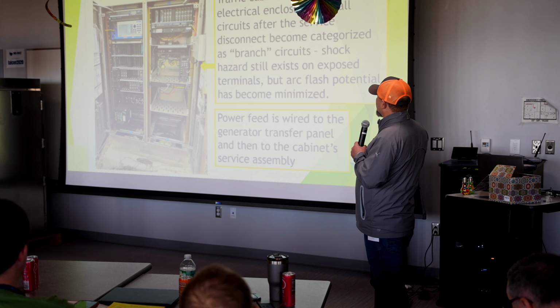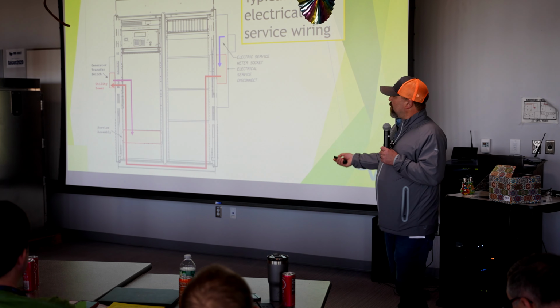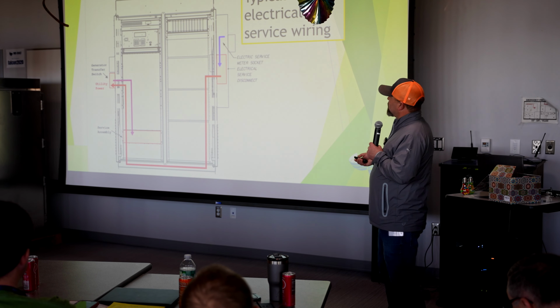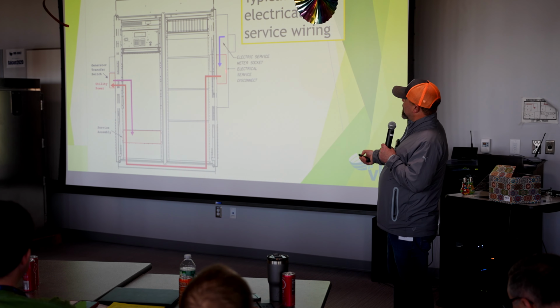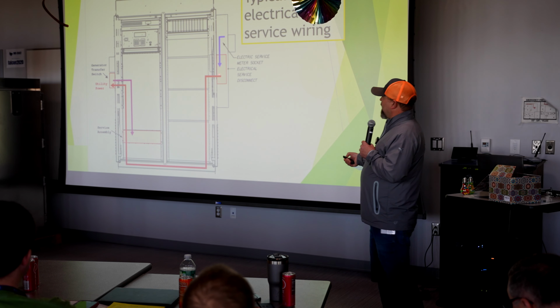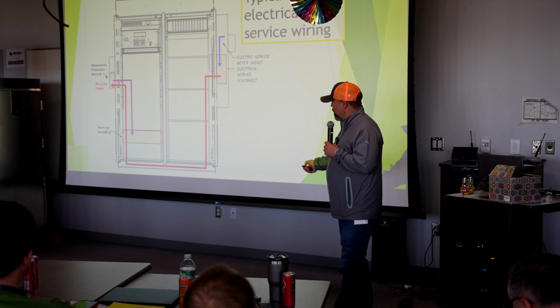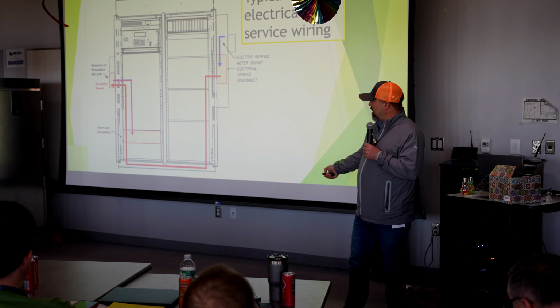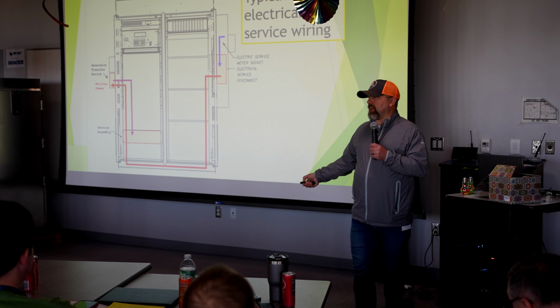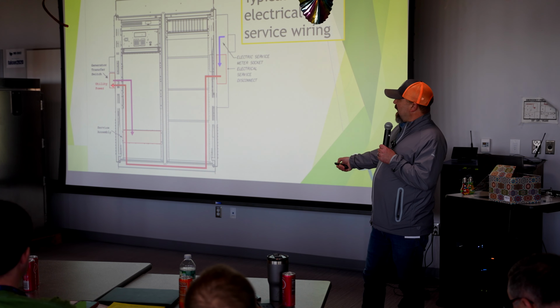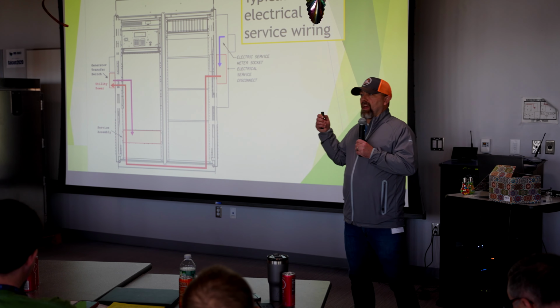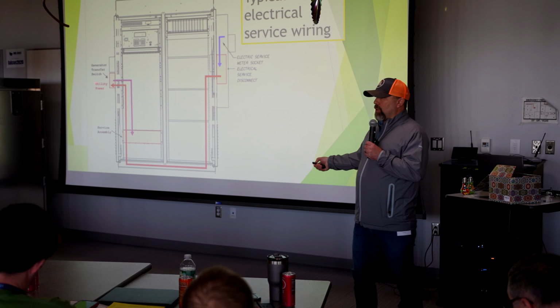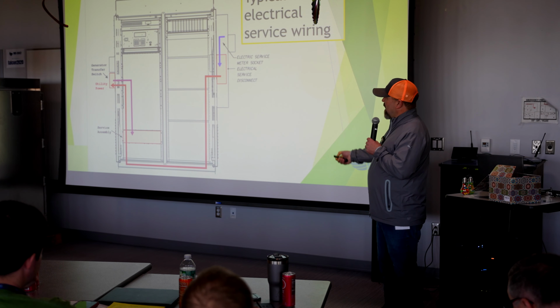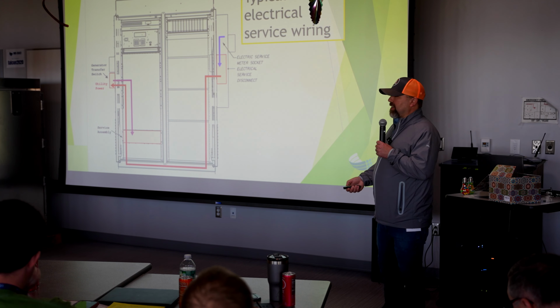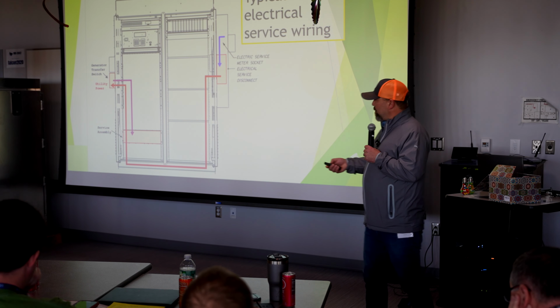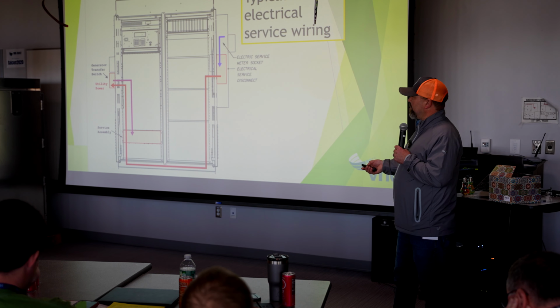I'll start speeding things up a little bit. But in general, when you're looking at how the power is wired in these cabinets, you've got your meter trim on the side, your service disconnect here. I'm finding most contractors run those branch circuits down along the skirting, either above the skirting or in this area, and then back up. So it's crucial to keep in mind that the feed is coming through your manual transfer switch and then back out of it through the contacts in that transfer switch to the service assembly. So this is typically what you should see.